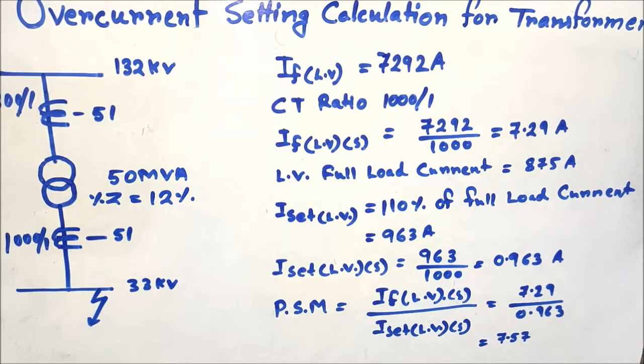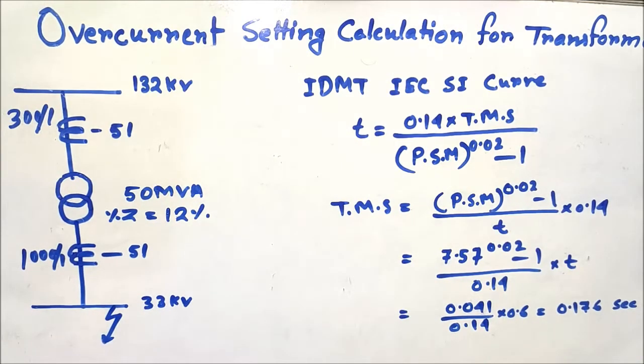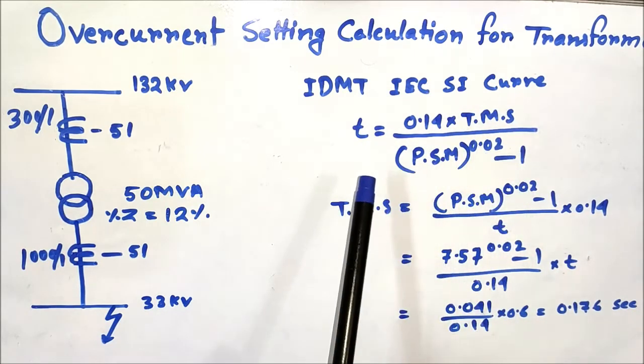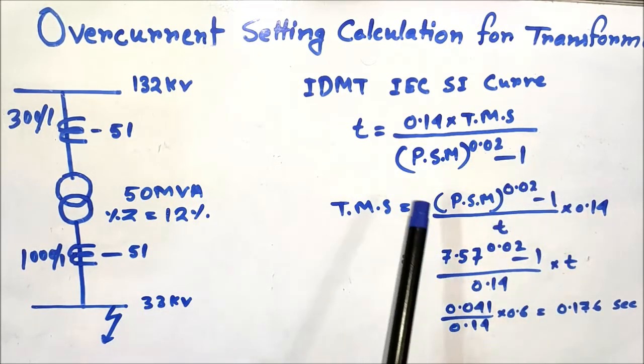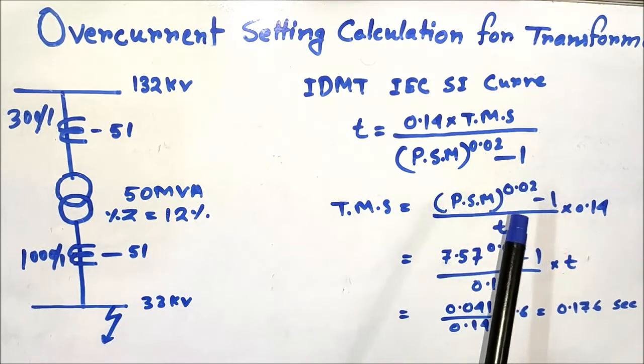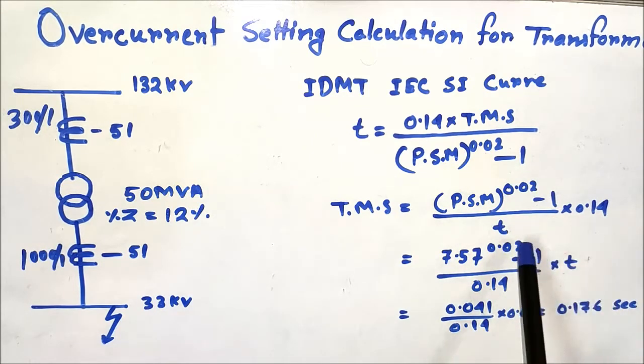Now we will calculate the TMS — the time multiplier setting — of the LV overcurrent relay, considering that it should trip within 600 milliseconds under maximum fault current conditions. As per the IEC standard inverse (IDMT) curve, the trip time formula is: t = 0.14 × TMS / (PSM^0.02 − 1). Rearranging for TMS: TMS = (PSM^0.02 − 1) × t / 0.14, where the trip time t is 0.6 seconds.